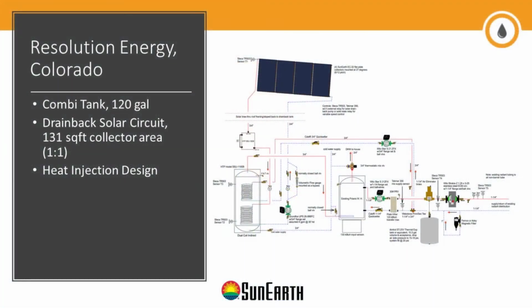So this is the system design: an integrated buffer tank type design, combi tank, drain back circuit, with a low collector-to-storage ratio of 1 to 1, and a heat injection design. All the solar circuits are happening over here, and this was a retrofit, so it wasn't originally designed with solar thermal for the radiant system.